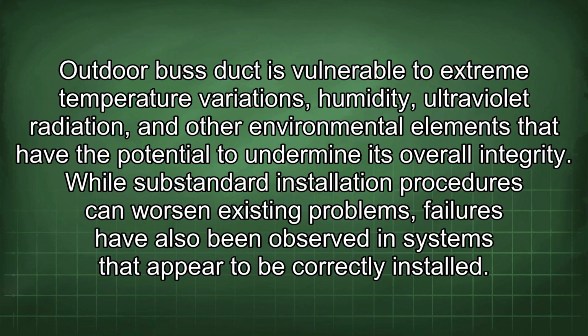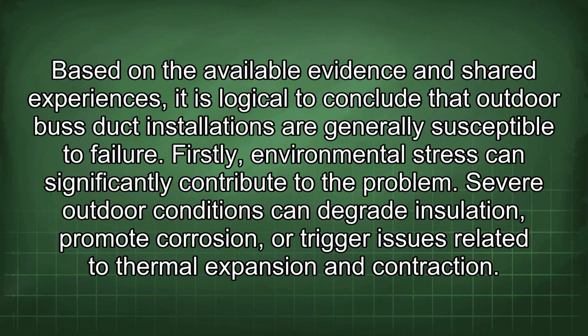While substandard installation procedures can worsen existing problems, failures have also been observed in systems that appear to be correctly installed. Based on the available evidence and shared experiences, it is logical to conclude that outdoor bus duct installations are generally susceptible to failure. Firstly, environmental stress can significantly contribute to the problem. Severe outdoor conditions can degrade insulation, promote corrosion, or trigger issues related to thermal expansion and contraction.